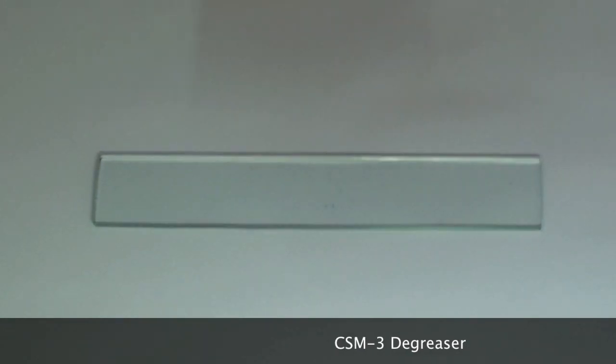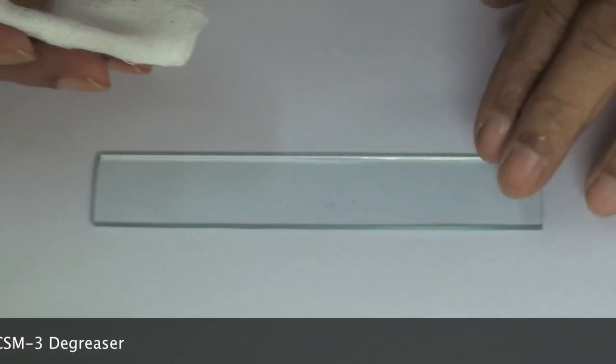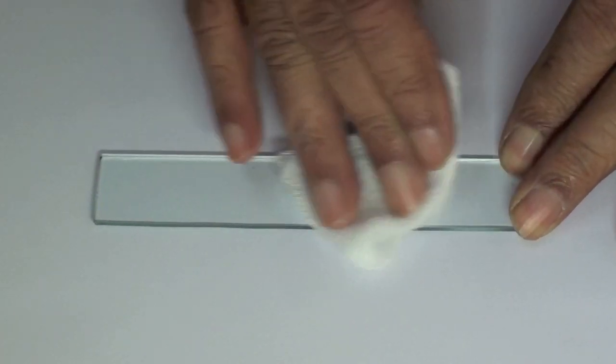The first step in strain gauge installation is degreasing. This is achieved by spraying CSM-3 degreaser on a gauze sponge and wiping the surface of the beam thoroughly to remove all traces of oily and greasy substances that are detrimental to gauge bonding.